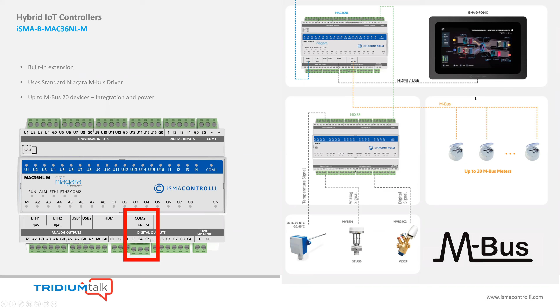But let's take a look at the details of the controller. Underneath Niagara is a unique Linux distribution called ISMA OS. The controller works with Niagara from version 4.4 and runs on a 1 GHz dual-core processor. All information from the controller, Niagara, and the user files are stored on a 4 GB micro SD card, and this allows for hassle-free on-site hardware replacement as well.